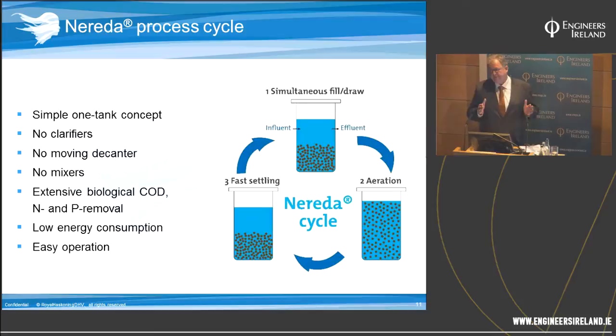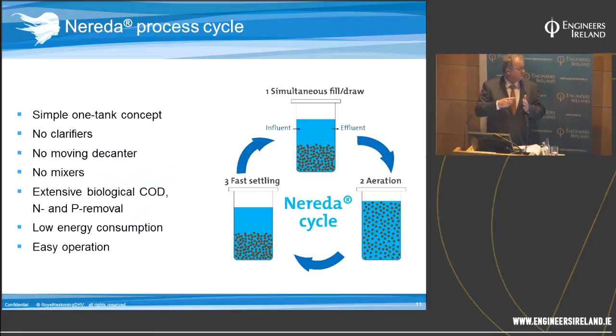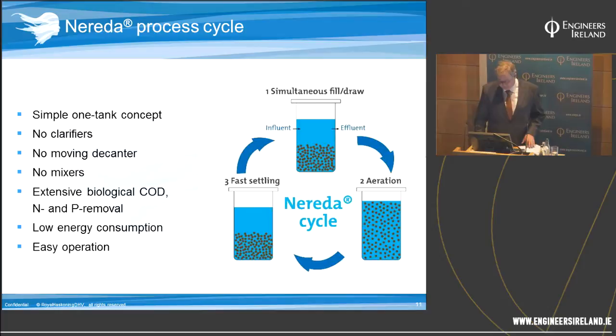Compared to a conventional SBR system, there are two notable differences. The time it takes to settle the sludge is much shorter — so after aeration you can start drawing the water much more quickly. Also, in the Nereda system we fill and draw at the same time, so cycle times are much shorter than a conventional SBR. We can also achieve higher mixed liquor suspended solids concentrations.